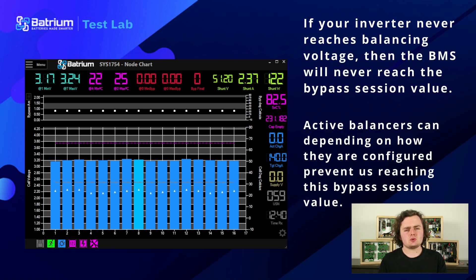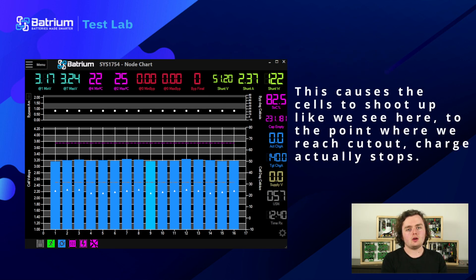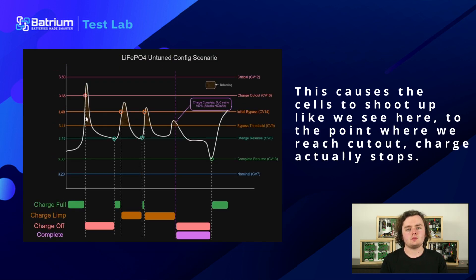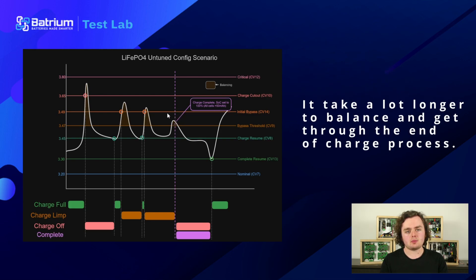Another thing that can happen: the charger might not behave the way we expect if it has its own limits or internal control loop. If a charger is very trigger happy or slow to respond, we end up pumping a lot of current into the battery at the end of charge, causing the cells to shoot up. It's a lot spikier — they shoot up all the way to the charge cutout value, which stops charge for a good while until we hit the resume value, and it takes a lot longer to get through the bypass process to bypass complete.